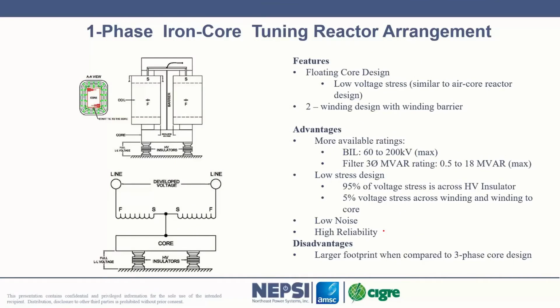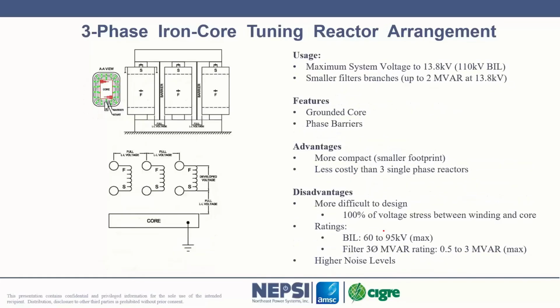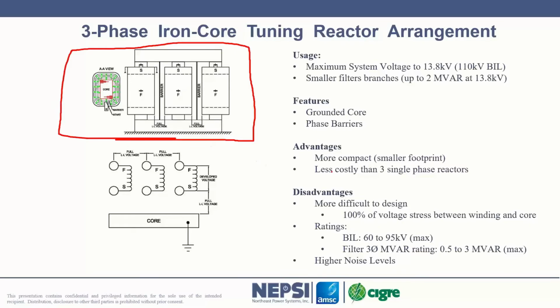So this is a picture of an iron core reactor, single phase. I don't have time to get into it in too much detail, and do realize that for smaller systems, oftentimes 3-phase iron core reactors are being used. This is typically at the 15 kV level. We might get up to about 3 MVAR; a filter tuned to the 5th harmonic would be a typical size, 3 MVAR. Oftentimes also the BIL, we're going up to maximum 95 kV BIL.